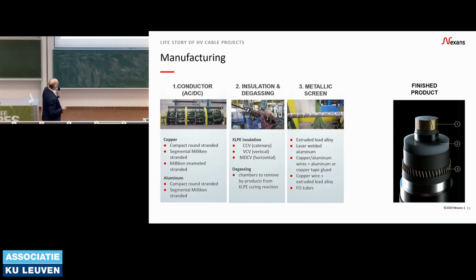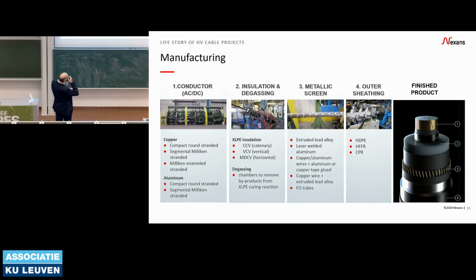In terms of cable production, I'll go very fast on that. It's just showing you that a cable seems simple, but it's not. The technology requires being able to make the conductor with Milliken, so multi-segmental conductors for AC, for example, and to manage the XLPE, which is totally different between AC and DC. This is not the same raw material, because in DC you have space charge problems in your insulation, creating other phenomena you have to manage.